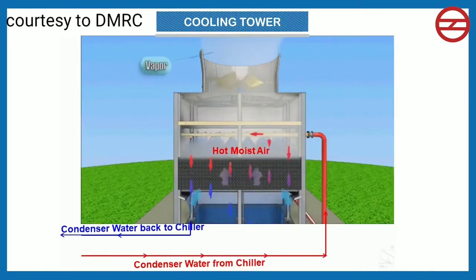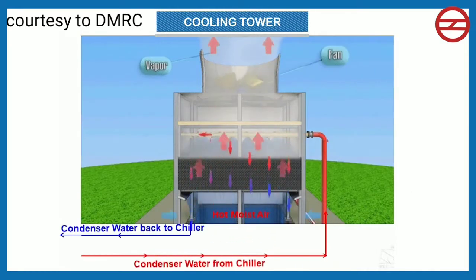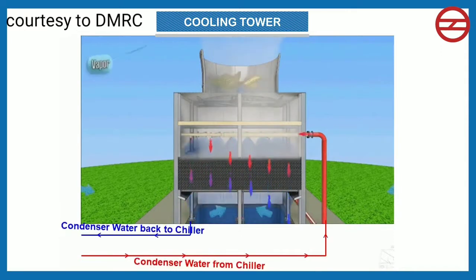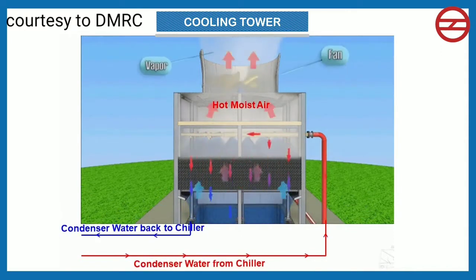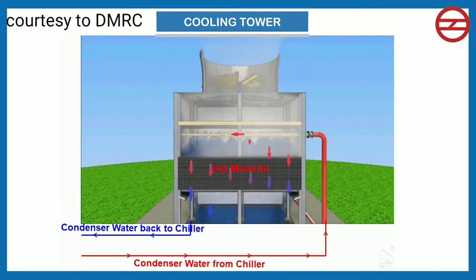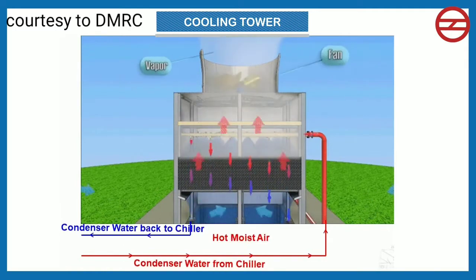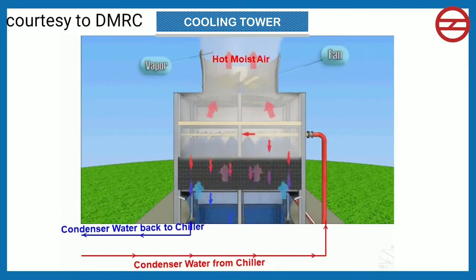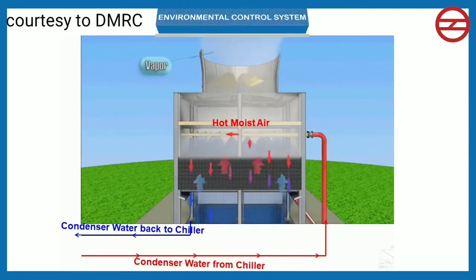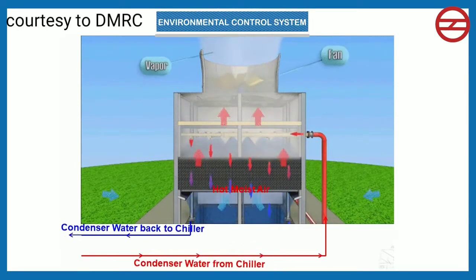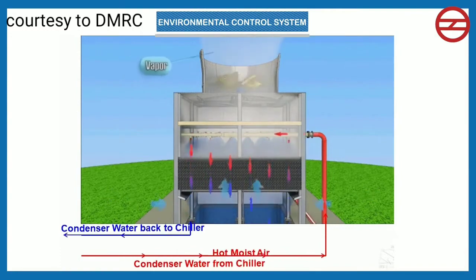Next component is cooling towers. Cooling towers are heat removal devices used to transfer waste heat to the atmosphere. The heat gained by condenser water in the chiller's condenser is removed in the cooling tower for reusing the condenser water in a cycle. Here you can see the entire environmental control system of an underground station.